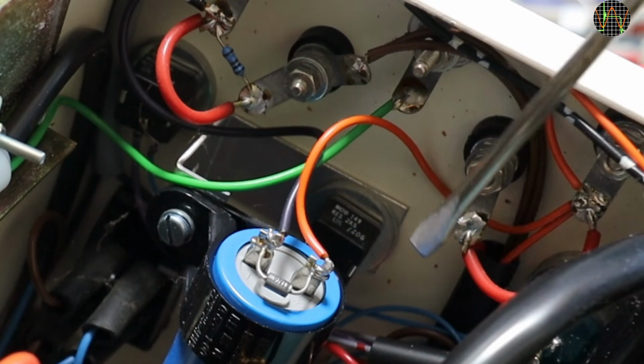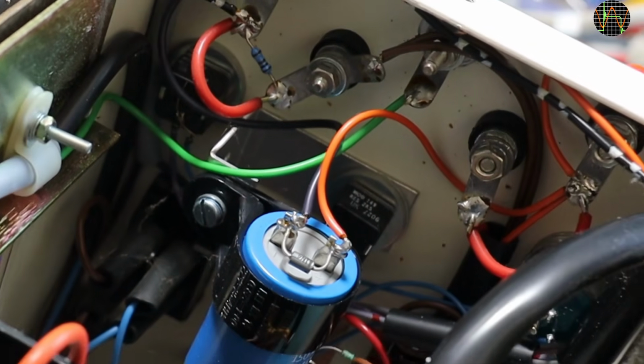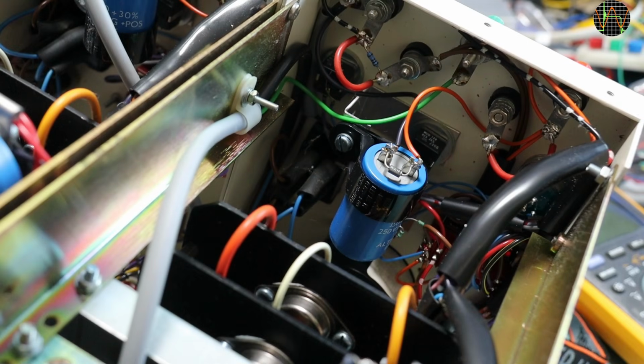Although the unit supports 4-wire mode, it is shipped with these links in place. To use 4-wire mode they have to be removed or cut, and from then on you must provide your own links on the outside when not using 4-wire mode.